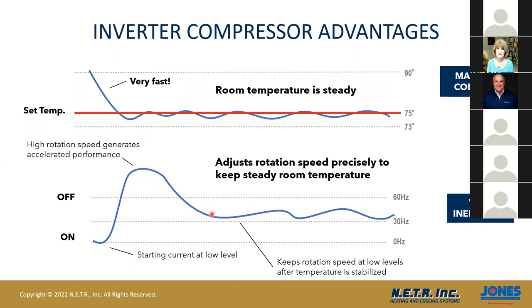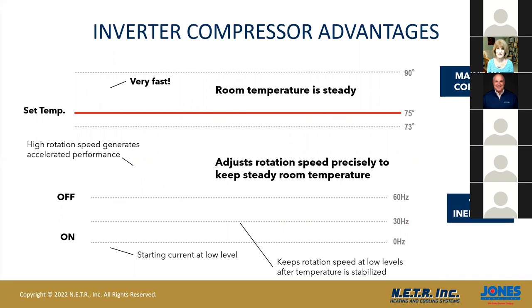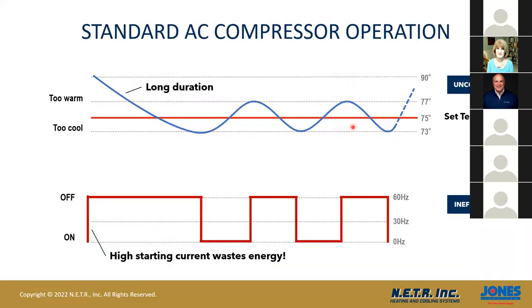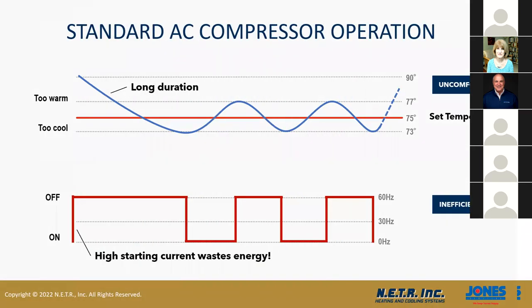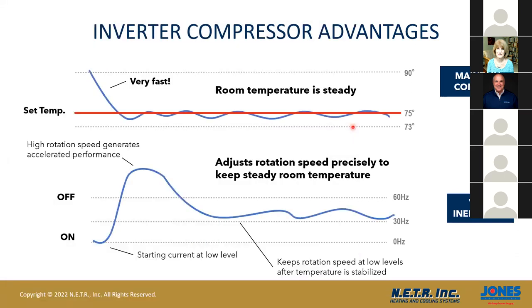The ramp starts, and the inverter slows the compressor down and brings it down to 30 Hertz. So we're not running at 60 Hertz, we're running at 30 or below. We slow down the indoor fan on the unit and run at a nice fine line of temperature. We don't do what I showed you prior. We're not doing the on and off. We're speeding up and slowing down with temperature, and we're decreasing the amount of current used on the compressor. That's what brings our comfort and our efficiency.